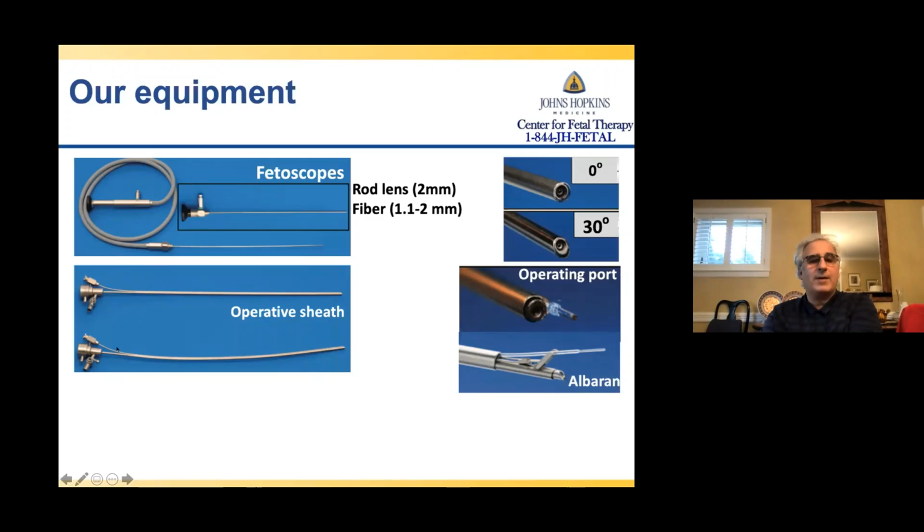One of the things that's the bane of our life is these attachments here, they are at non-standardized angles. So sometimes they have such an angle that certain instrumentation you couldn't actually push through it. Whoever planned that is beyond me. It makes no sense whatsoever. And in some cases, these channels on the inside damage the instruments so that we have to use multiple laser fibers because the tip is broken up and it affects the precision.